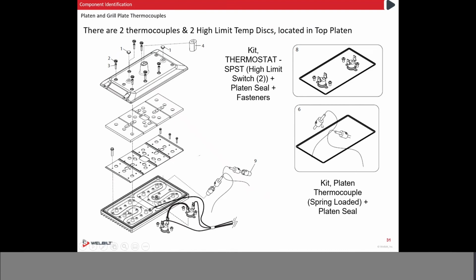Also, you have the two thermocouples that are being replaced with a gasket, but you're not doing the conduit harness. On the Chick-fil-A unit, there's enough room in the conduit that you can actually fish the thermocouple through the conduit. So just keep that in mind. You don't have to cut the wires to run the thermocouples. You'll be able to fish it through there.